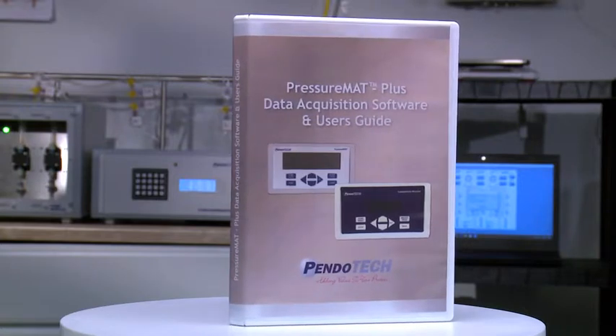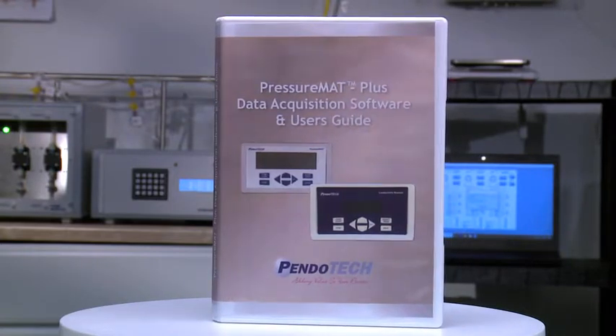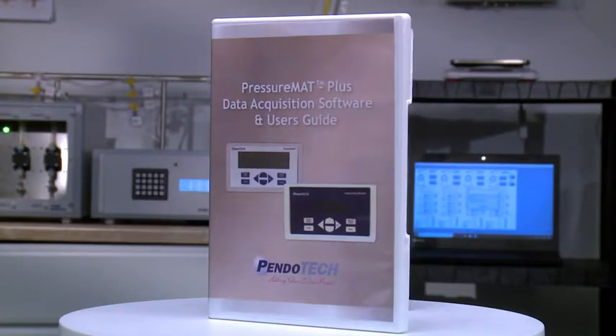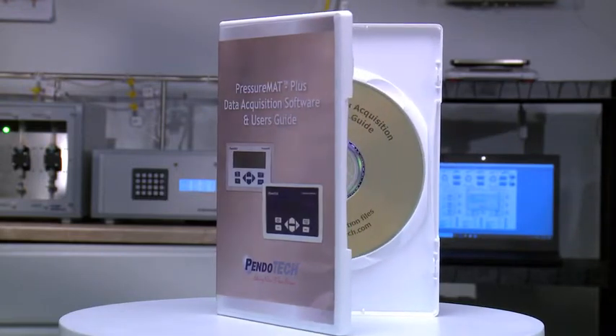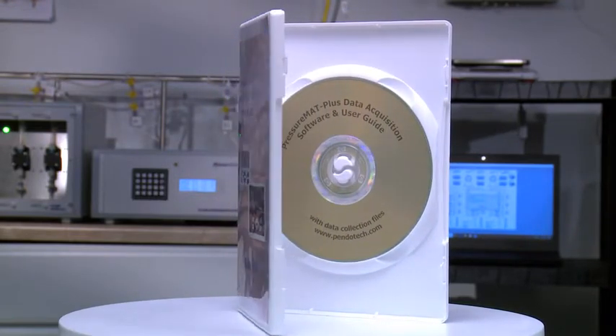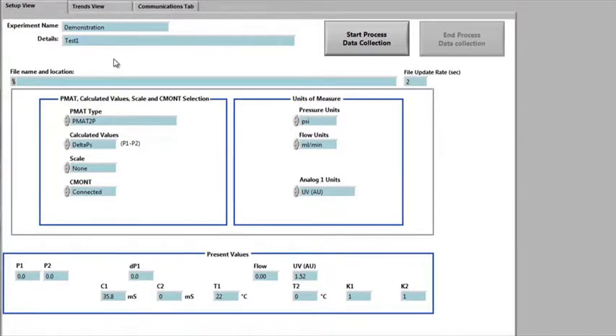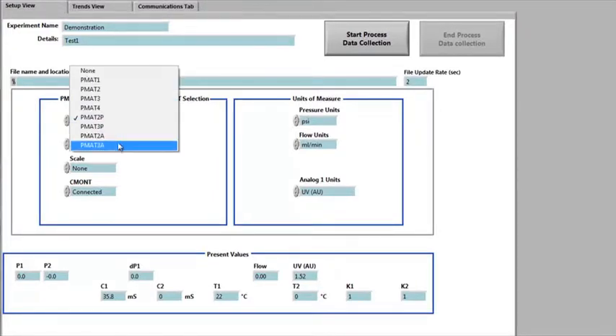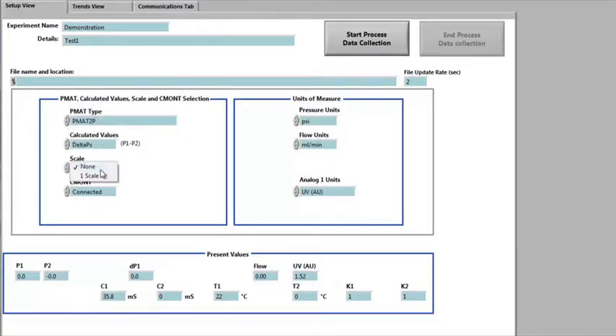PendoTECH offers the PMAT plus GUI software package that can be used to trend the data real-time and log the data to a file for future use. The software can also log data simultaneously from the Pressure Mat or the Pressure Mat Plus monitor and one scale, creating a very powerful and inexpensive data acquisition system with up to 9 total data points being recorded.